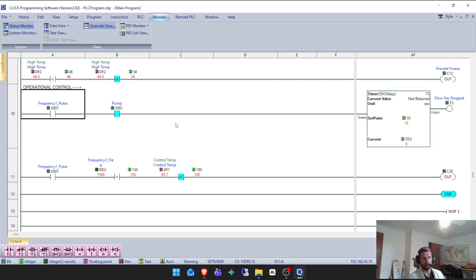So, for example, let's just say there's a valve that's restricting water flow. Your pump's on, but your manual valve that you forgot to open is not, and so you're just running this pump into a closed loop system. You'll burn out the pump. Or, of course, if you don't have any water flow, that's a huge problem. Let's just say there's a leak, there's a broken pipe, and the water's just spitting out, and there's no water flowing through this pump. You end up running into issues where you're not able to detect it without this turbine flow sensor.